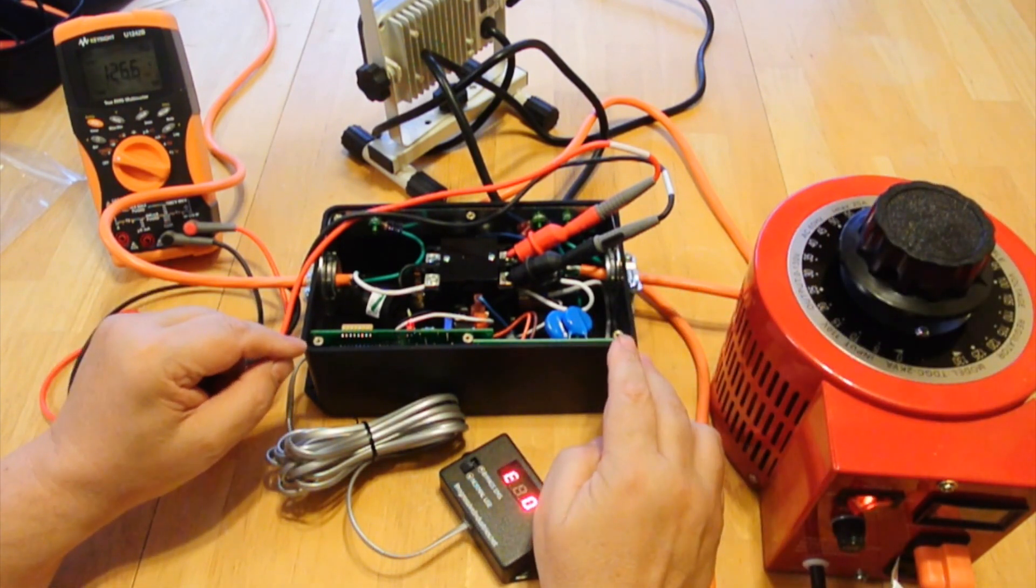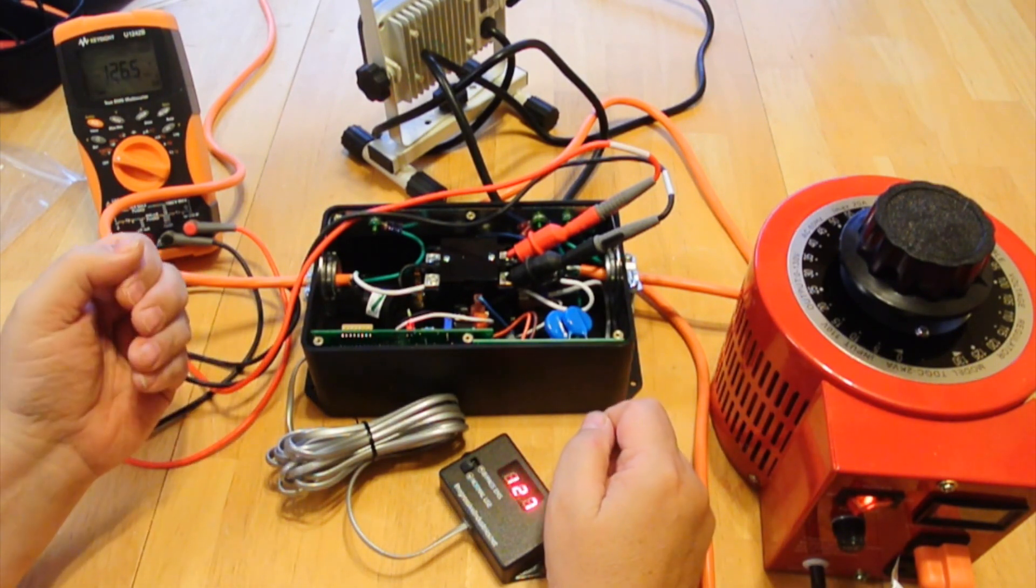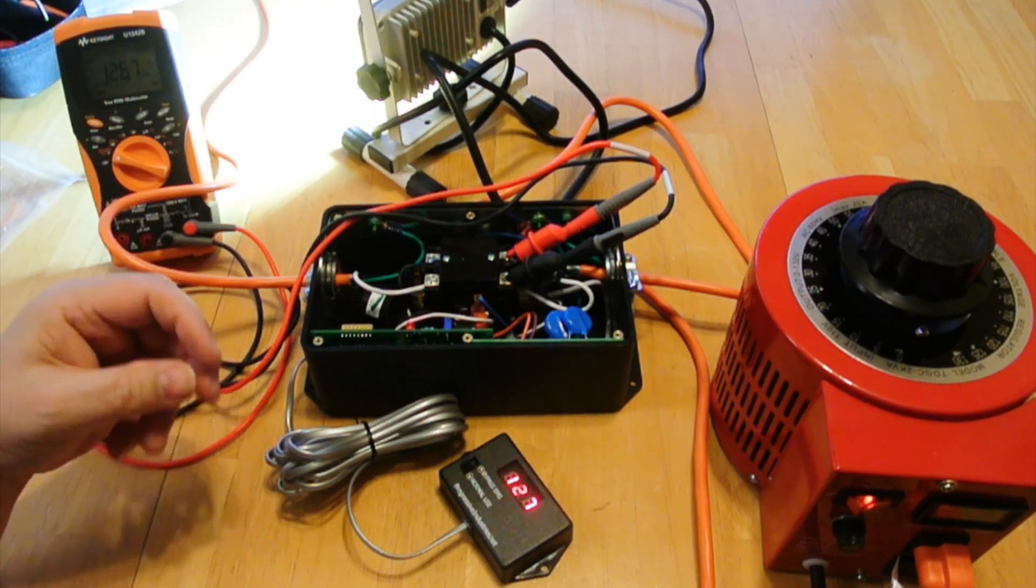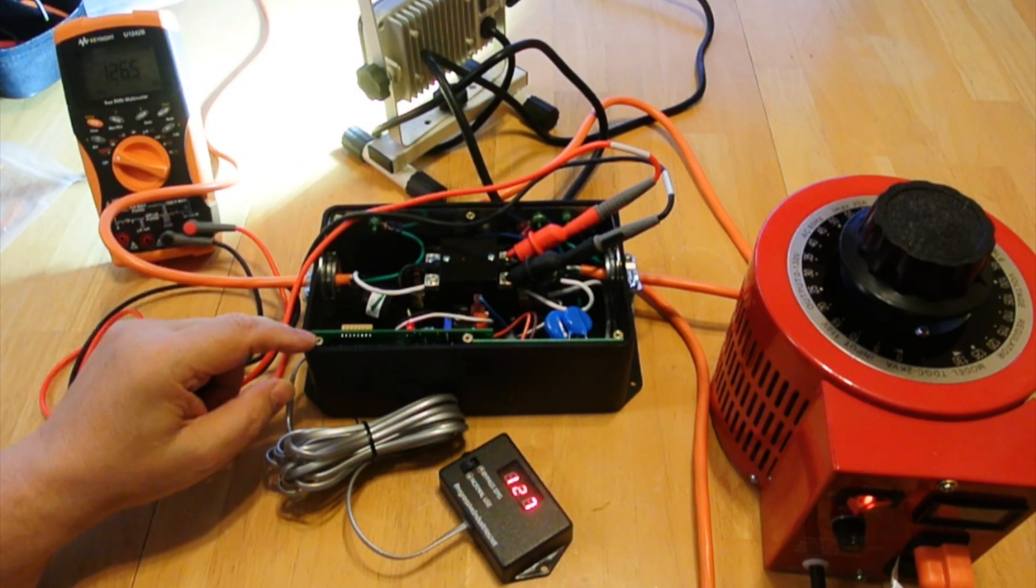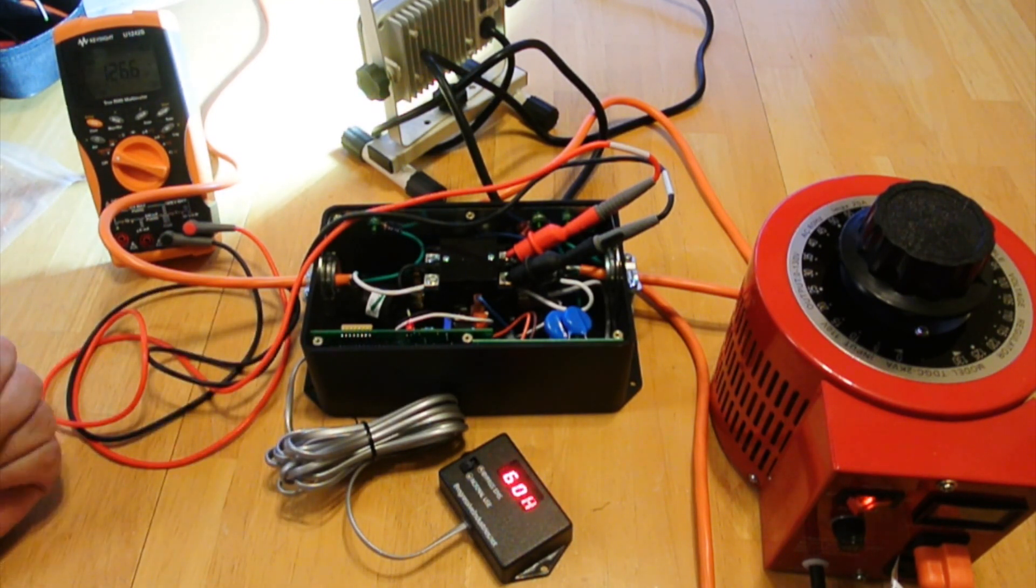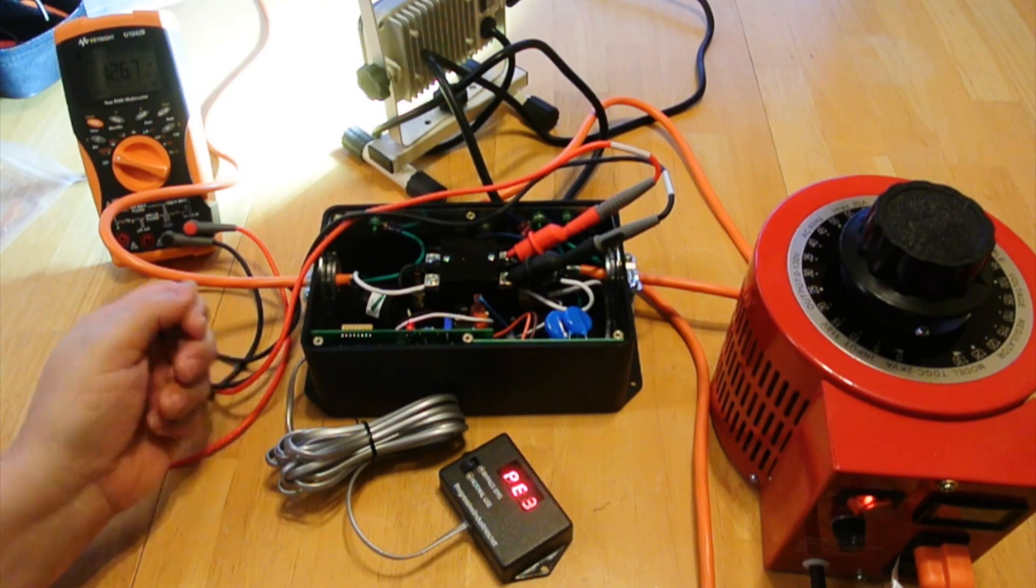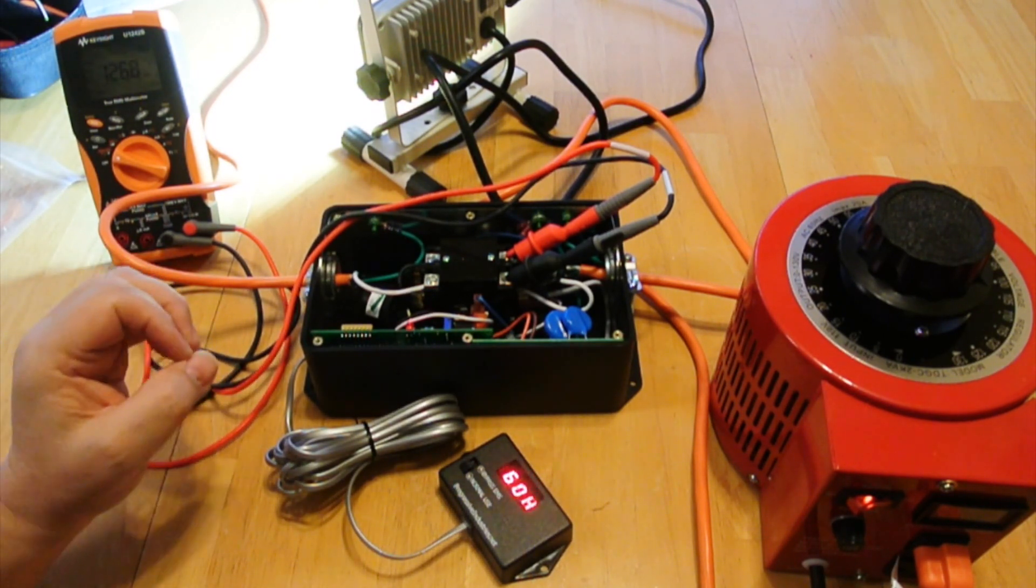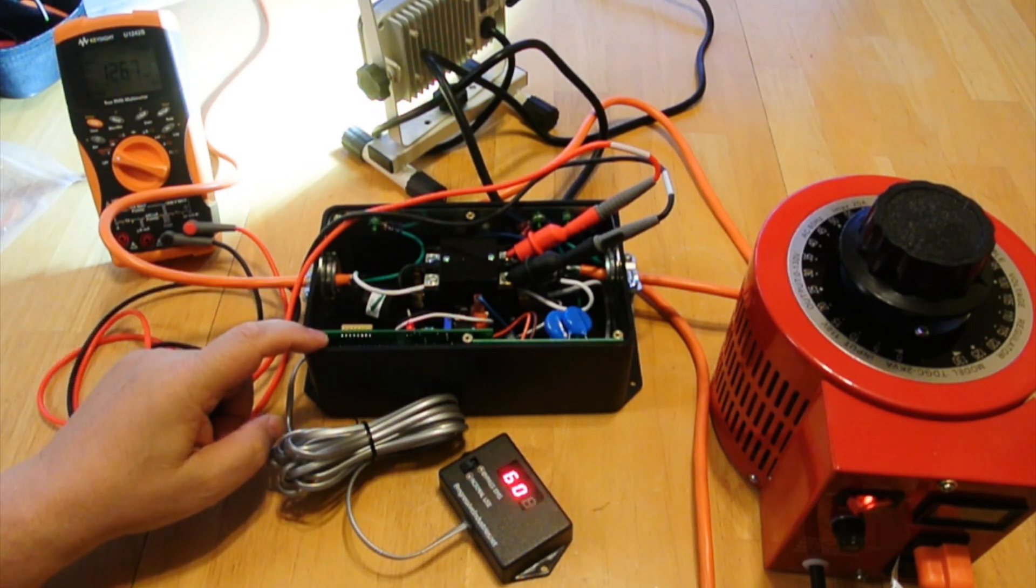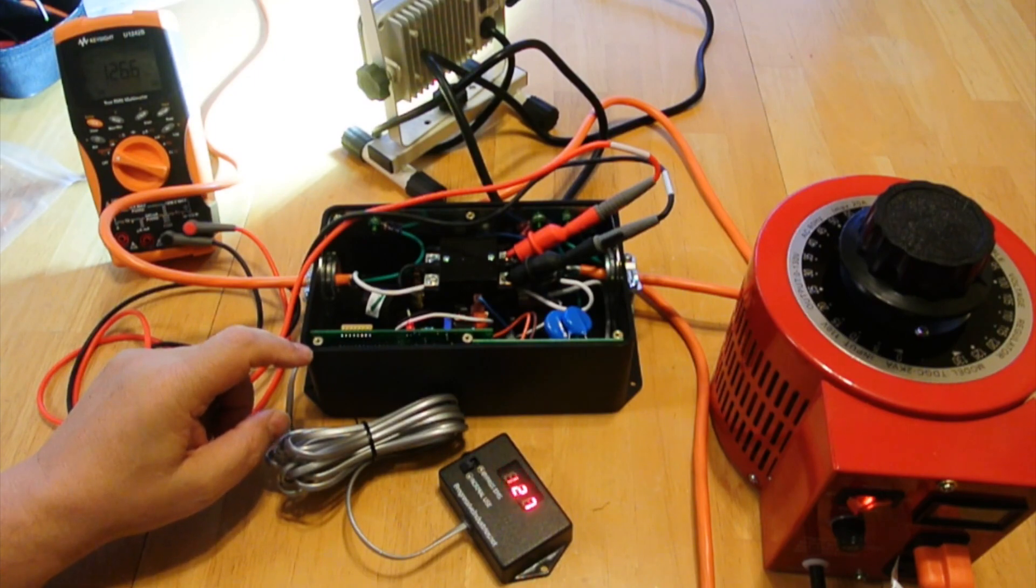And that delay is primarily because if an air conditioner was running, you don't want to short cycle an air conditioner. In other words, you don't want to turn the compressor on and off, on and off, on and off repeatedly because it can damage it. Now there's two settings in here. There's a 15 second delay, which is the factory default, and there's also a 136 second delay. So, which one should you use? Well, some air conditioners have their own delay. So with some air conditioners, when you turn the power off and then the power back on, it will delay itself as long as it needs before it turns on. If you have that type of air conditioner, you can set this for 15 seconds. However, if your air conditioner does not have such an internal delay, then you're going to want to set this for 136 seconds.